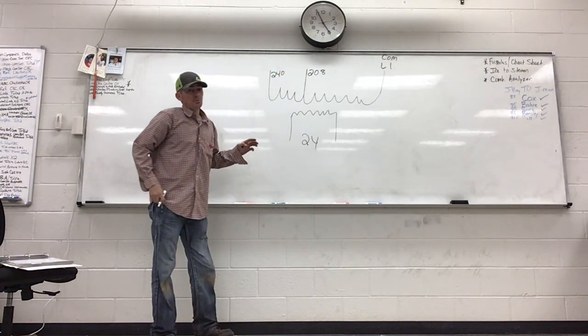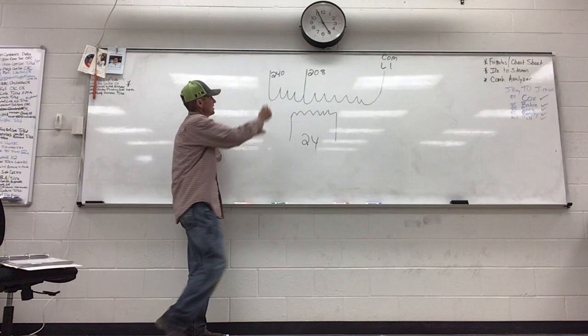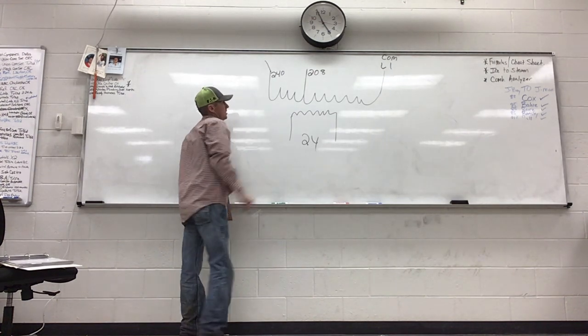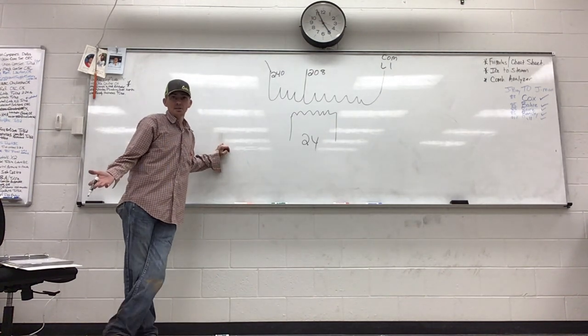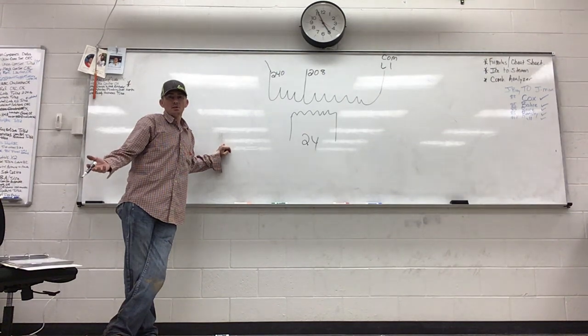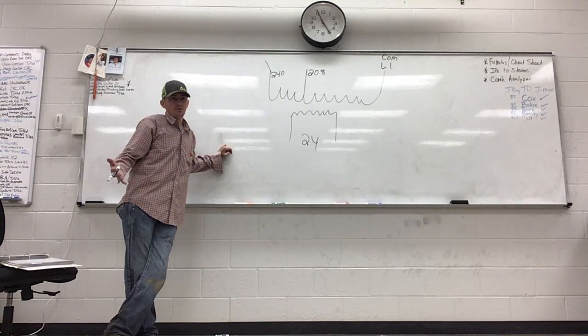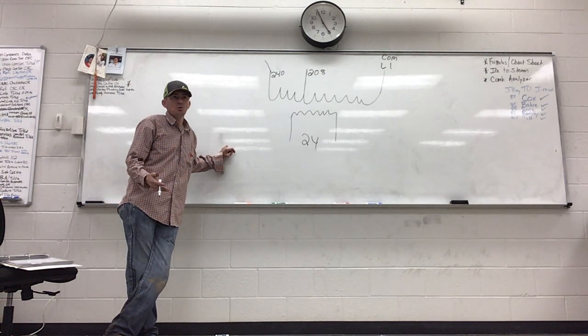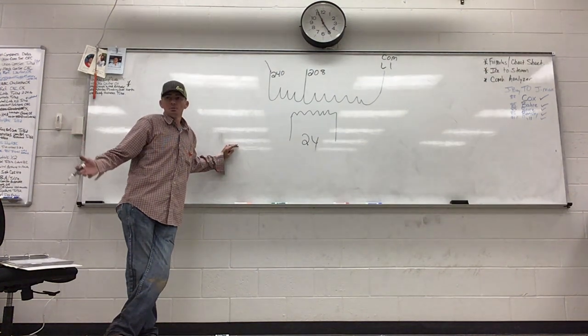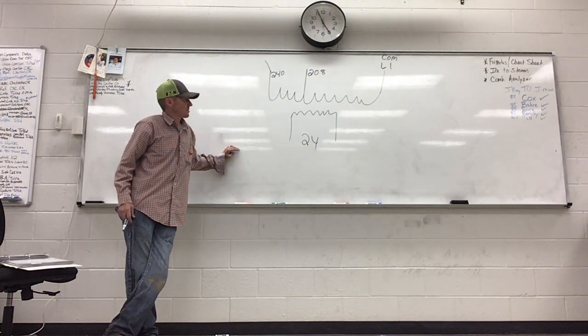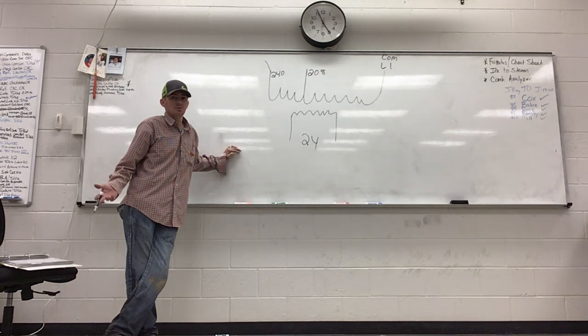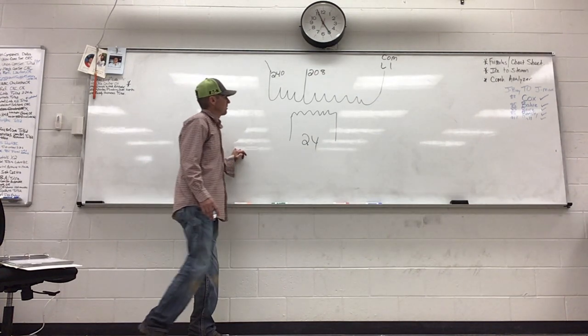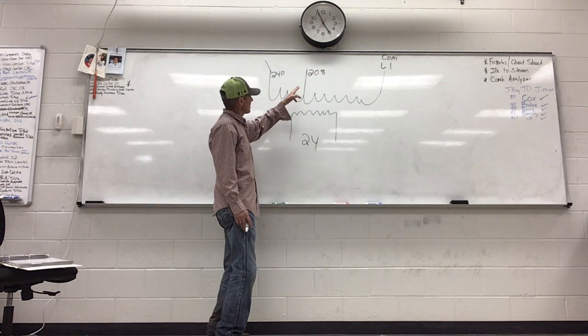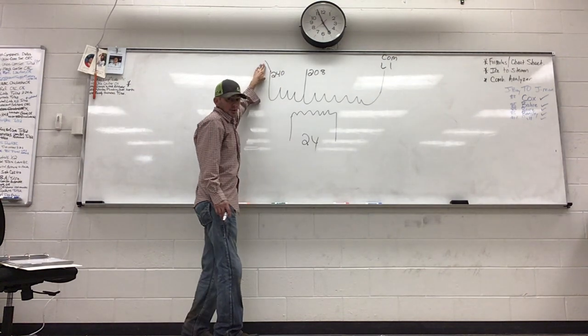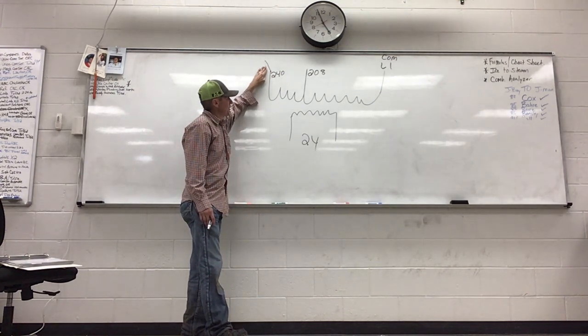Guys, every rooftop unit from the factory is going to be wired into 240. And I already told you guys the 240 Delta is way less common than the 208, unless you're working on a bunch of small buildings. But when we get into bigger buildings that have multiple units and stuff, most of the time it's going to be a 208 building. Not always, but majority of the time, I'd say. But from the factory, they're wired in for 240.